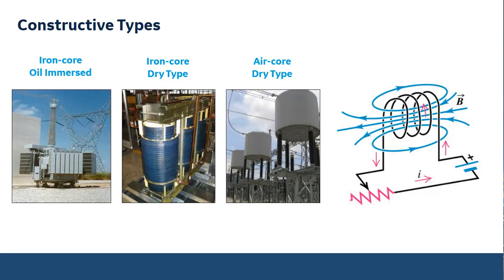So the air core dry type is a very common technology to use to add impedance to block fault current, basically because there is no core, there is no core saturation, and there is no impedance change. So this is related to the application. Now let's talk about the construction of the equipment. The air core dry type has a very simple construction. It's basically made of fiberglass encapsulated in epoxy resin. The wire that I mentioned before, the conductive material, is all encapsulated in this fiberglass and epoxy material. The reason for that is to protect the wire and the insulation from the outside world, not allowing water, humidity, sunlight, UV, etc. to reach the inside. And basically that's it. It's a big round cylinder made of fiberglass, aluminum, and epoxy.